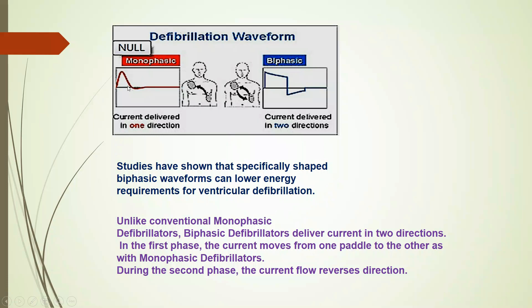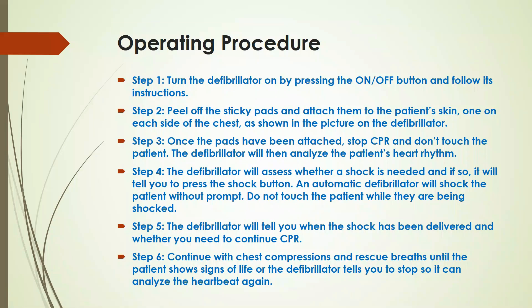There are two different techniques used for defibrillation: monophasic and biphasic. Currently the biphasic technology is used. Here is the curve which delivers current in a single direction, and here is the bidirectional biphasic curve which delivers current in two directions.